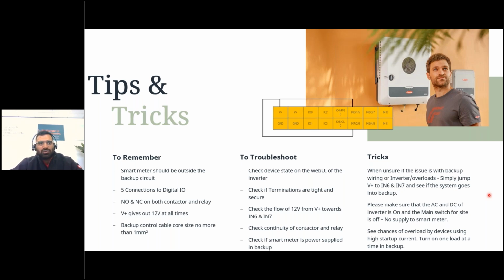One of the things you can also do is check why we are losing this 12 volt. We can check the continuity of the contactor and relay to see if they are really working how they're supposed to, or whether they are faulty. And of course, we also need to make sure the smart meter is not getting power supplied in the backup circuit again.